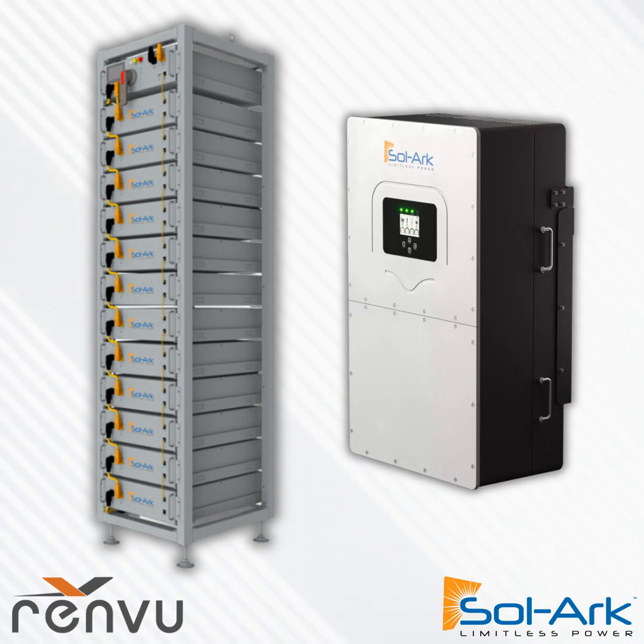For 208 volt, our indoor battery cabinets are 40 kilowatt hour stacks. For our 480 volt applications, a little bit higher AC voltage, also a little bit higher DC voltage, and it's a 60 kilowatt hour stack for our indoor on 480. So there's a difference in our indoor options between 208 volt service and 480 volt service. It's a 40 kilowatt hour versus a 60 kilowatt hour stack. These are very flexible stacks, and on our indoor options, you almost never run out of maximum battery capacity, but the increment of the battery is either in this 40 kilowatt hour or 60 kilowatt hour building block.